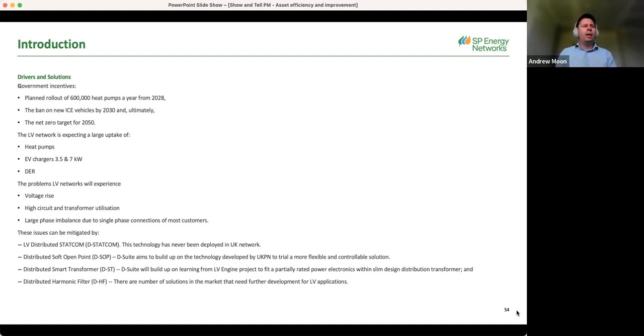We've seen two of these technologies rolled out previously on trial innovation projects, which brought the TRL up to its present levels. Those were the DST, which is a smart distribution transformer, and the DSOP, a distribution soft open point. They can do similar things to a certain extent, but the smart distribution transformer is mainly enhancing the functionality of a normal transformer, adding power electronic devices at either end on the LV and HV side. A soft open point does a similar thing without the transformer present, but at the end of the feeders and in between two different networks, and transfers power across two networks where it couldn't normally. This can improve load sharing across transformers, as I mentioned before.